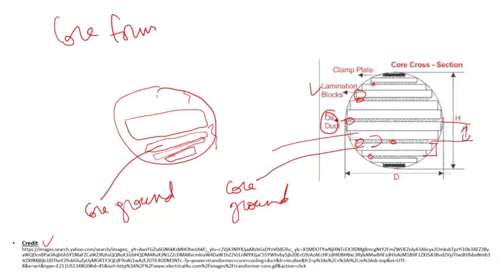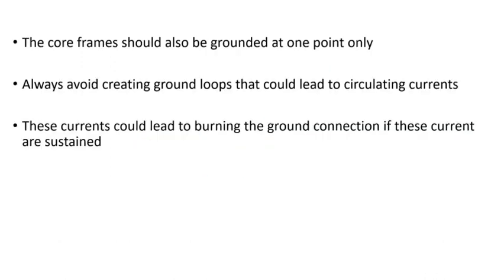But if you have cooling ducts, like in the case of large transformers, then either you need a core ground in each section that's created by the cooling duct, or somehow you need to bridge each two adjacent sections that are isolated by a cooling duct. That way you only have one core ground. It's always good to have just one core ground, because anything you add is another thing that can cause a failure. So that's the bottom line. Because all these things, you have to isolate them from any other conductor inside the tank. The core frames should also be grounded, because, as I showed in previous videos, the core laminations are held together top and bottom by core frames, core clamps. Those need to also be grounded at one point.